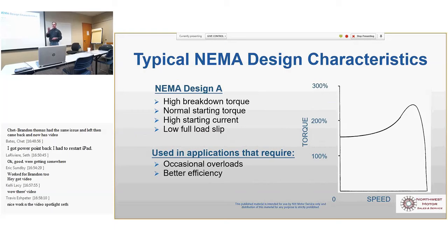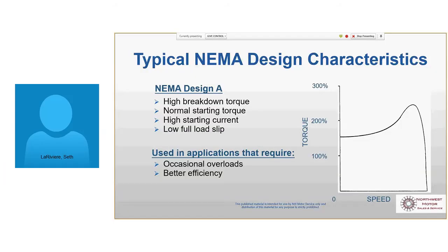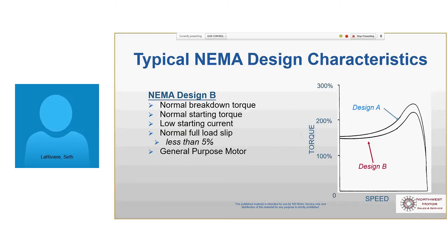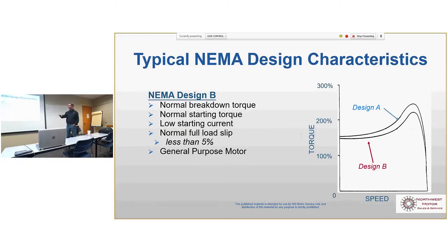So there's 4 different letters that define torque in a motor. They're called the NEMA Design. NEMA Design A is, I think a lot of your loads are kind of NEMA Design A to me. They're fans, easy pumps, centrifugal pumps, and all of our motors are suitable for A. Because A is kind of the easiest, and this is what the torque looks like, the speed torque curve. B is what's considered standard. So these are NEMA B motors. So the way it works, if it's a B, it'll do everything beneath that. So it will do A. If it's a C, it will do B and A, like that.